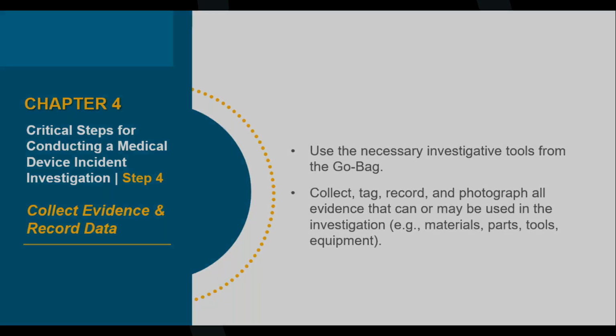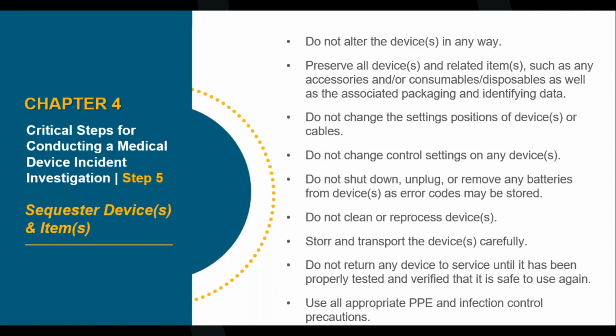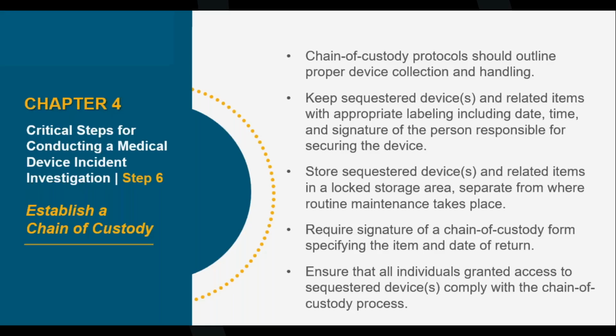Then we're going to sequester the device and any consumables or disposables. At first, we don't want to alter the device in any way. We don't even want to look at the logs, just capture what is there. Preserve all the device-related items, such as accessories, consumables, disposables, and the packaging for consumables and disposables as well, because you're probably going to want that lot number. Do not change the settings or position of the device, don't change control settings, don't shut down, unplug, or remove any batteries. Do not clean it at first. Store and transport the device carefully, and do not return any device to service until it's been properly tested and cleared for use. And again, use your PPE.